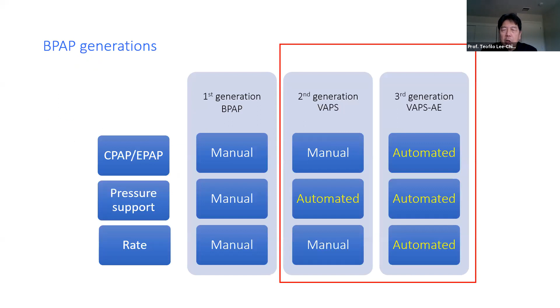In the second and third generation, we have automated some of the features. This was discussed earlier by Aref. So this is an example of your second generation volume assured pressure support. You still have to manually enter your EPAP, in blue in the foreground, but the machine will automatically alter the IPAP, therefore changing the pressure support, whenever the tidal volume drops below your target levels. And we will discuss this in more detail in the next few slides.